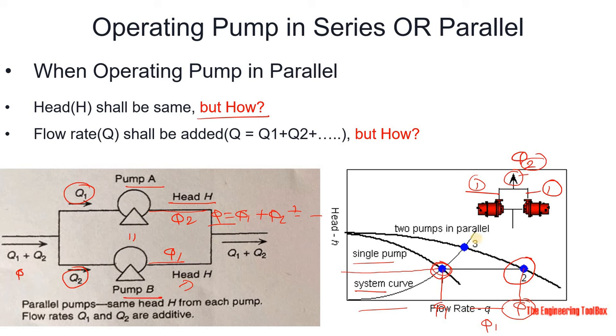In a practical scenario, the combined flow Q and head will not match the theoretical prediction exactly — the actual operating point on the system curve will be somewhat different. The head obtained is lower than the theoretical value. When two pumps running in parallel or in series, if one pump stops for any reason, the system curve operating point will return to the single-pump condition.